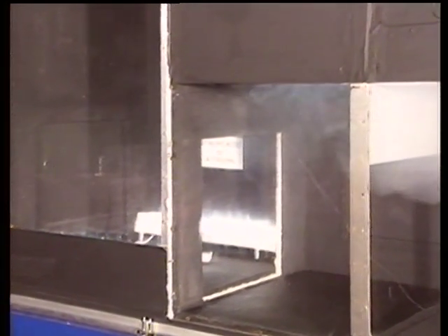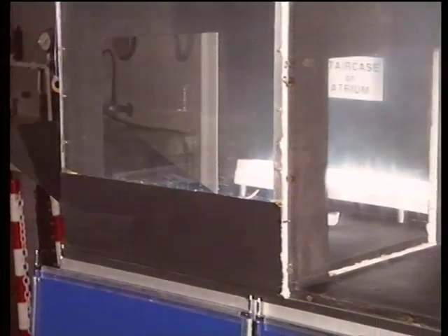As you can see, as we close it off, immediately that smoke starts to come down below the screen and back at low level, thus creating a smoke log situation. Similarly, if we cut off the extraction rate, the gas layer would come down. If we didn't have sprinklers within the fire room, the fire could go beyond the fire room to flash over, in which case the system would break down anyway. And if we didn't have screens, the gases would go beyond this section of the shopping mall into other parts of the shopping mall and cause smoke logging at remote locations within the building. So all four measures are needed, and we'll open the inlets again just to demonstrate the safe condition which we just had a moment ago.